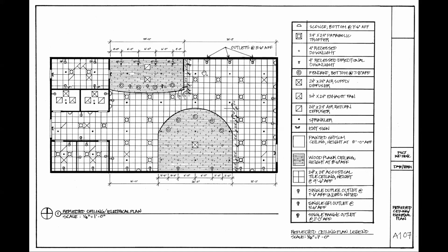And you can see here, these are placed every, let's see, 12 feet. No matter what, it doesn't matter what's inside, what's in the way, their location is set because they have a spray around their perimeter that creates a circle, and that spray needs to overlap with the one next to it. So that's what those little dots are for.